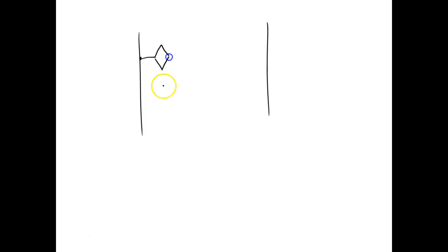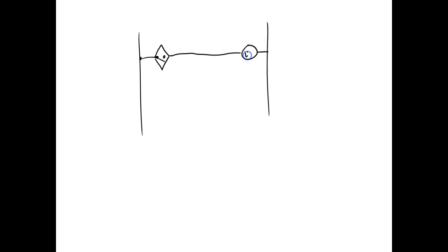So what we got is a solid state sensor. Another problem with solid state sensors is they have to be powered up to work. So a lot of our solid state sensors, what you're going to see is it comes up, and what's the symbol for a solid state sensor? It's going to be a diamond shape, and it's going to have a contact in here, usually normally open. Then it's going to come over, and our load is going to be right here. That could be a relay, a solenoid, or a light, right?